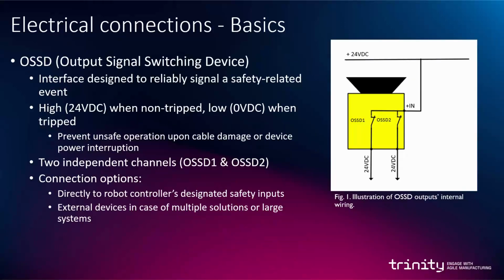We will begin by looking at the basic connections that are found on safety scanners. The OSSD or Output Signal Switching Device is an interface designed to reliably signal a safety-related event. It is designed so that when a safety violation has not occurred, the OSSD outputs are in a high state or 24 volts DC. When a safety violation occurs, they immediately switch to low state or 0 volts DC. This is to prevent unsafe operation upon cable damage or device power interruption.